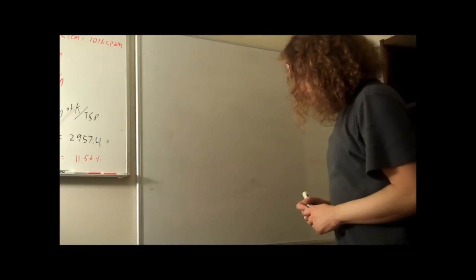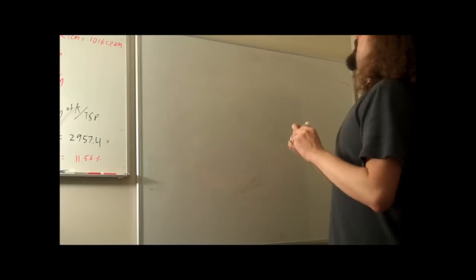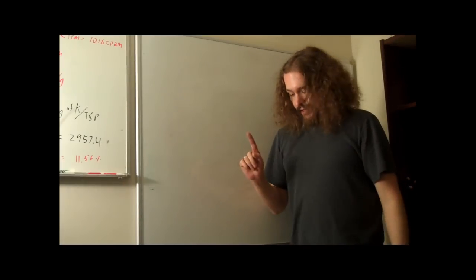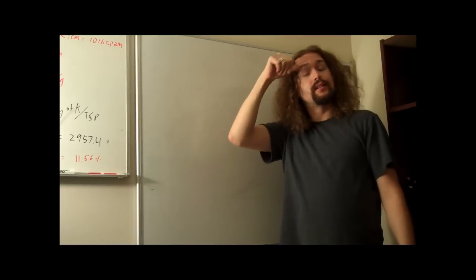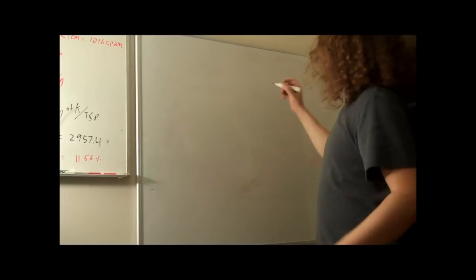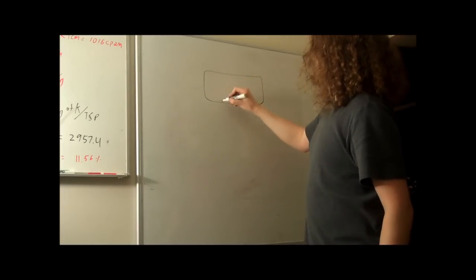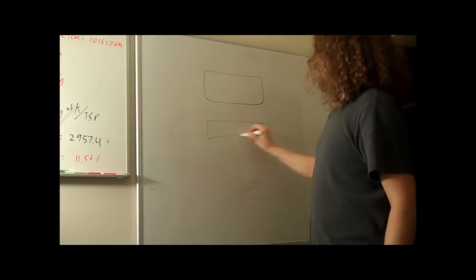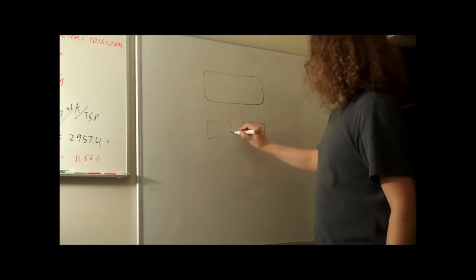Alright. Polonium 210 calibration. The activity of that disk is 3,700 decays per second. 3,700 becquerels. This is the Geiger counter. Here's the check source. It has a little dip in it.